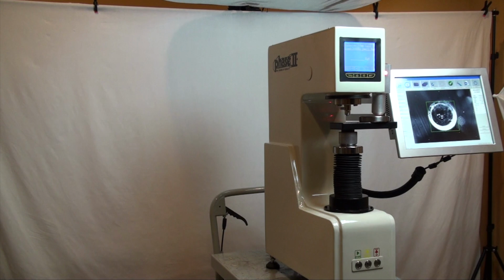Let's begin with the unique design of this series hardness tester. The maximum workpiece height is 200 millimeters, or just shy of 8 inches. The maximum workpiece depth is 140 millimeters, or just shy of 6 inches. Here we have a digital camera that is used after the indentation is made. This will enable the screen control here to analyze the image from the indentation and give a direct hardness reading.